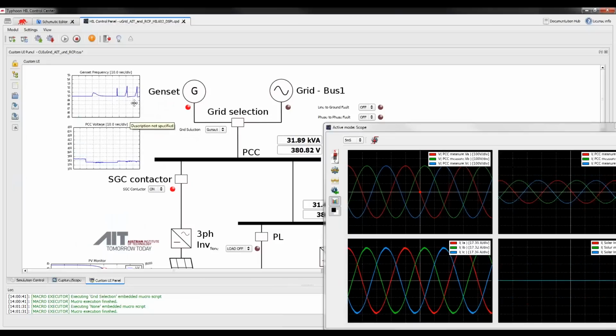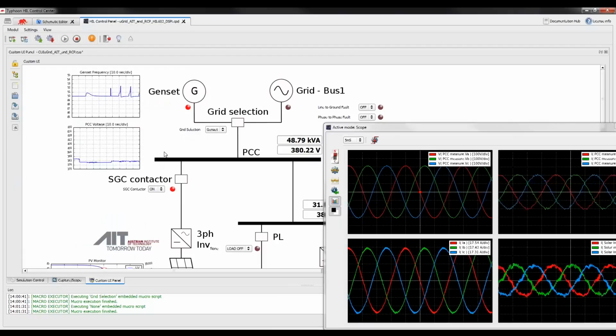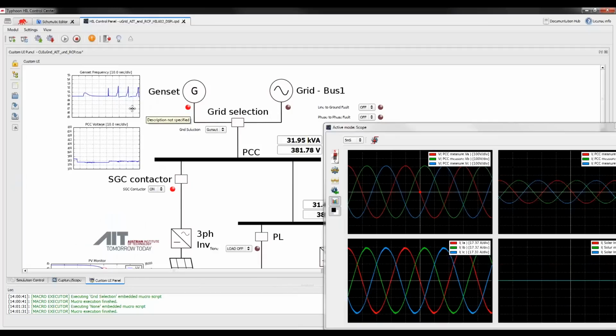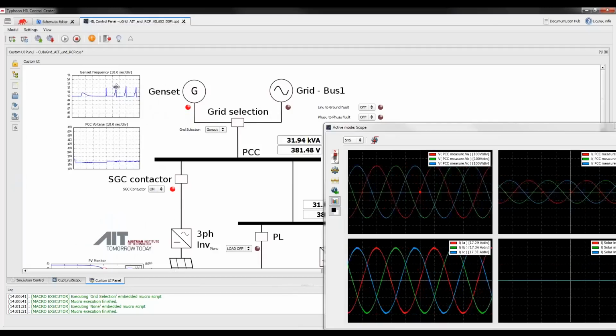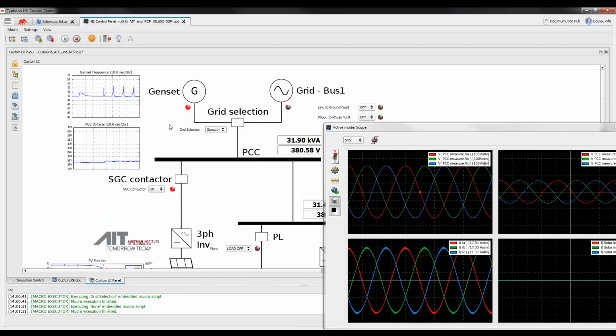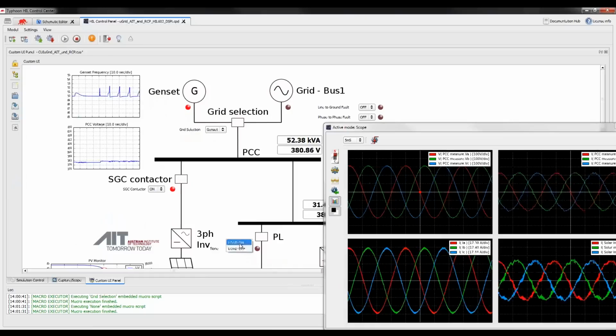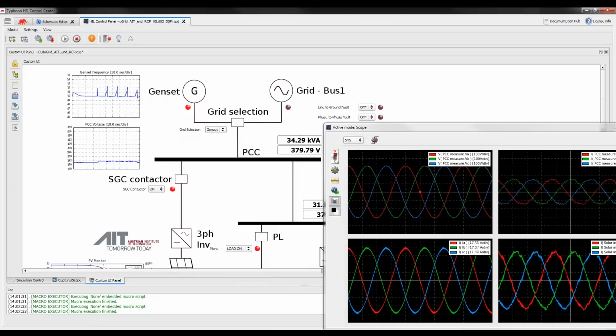So this is an interesting, simple example of oscillatory behavior where the limits on the frequency regulation are forcing us into the shutdown mode on the PV injection, and then we are reconnecting back and trying. You can see these spikes every single time the solar inverter tries to connect. It's basically coming back and getting disconnected. Now, if we add a little bit of load in this process, because load and generation are better matched, the frequency swings are a little bit more moderate, tamed, and we are able to quickly get the frequency of the microgrid in island mode in the proper regime.